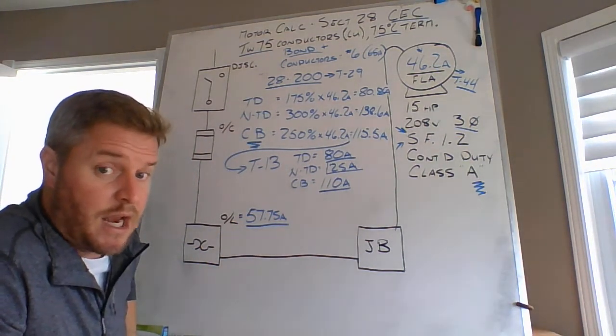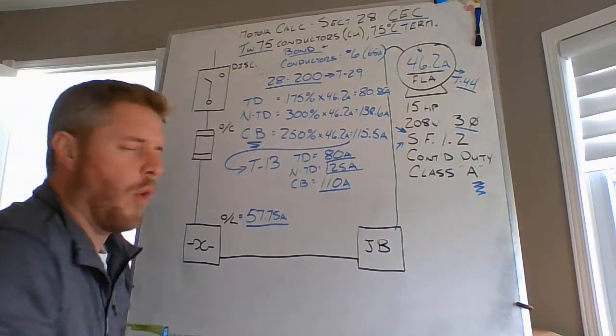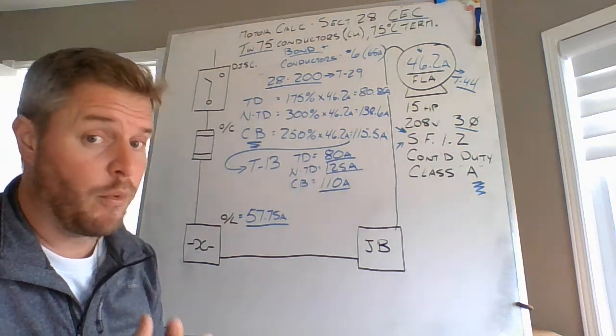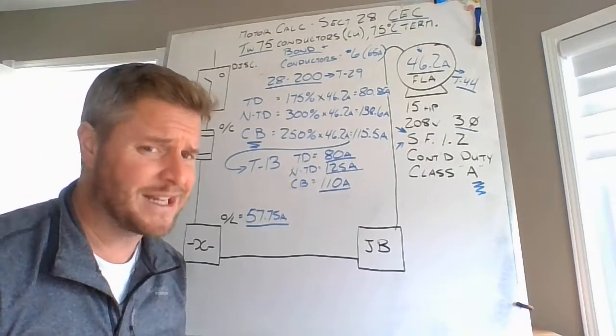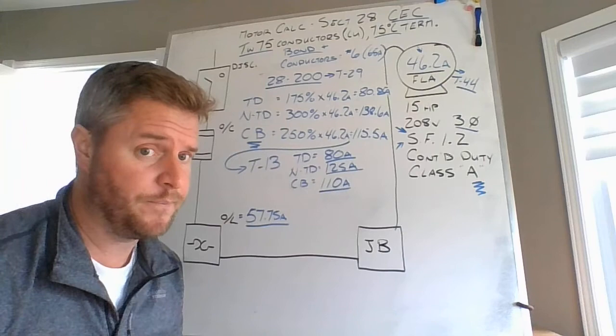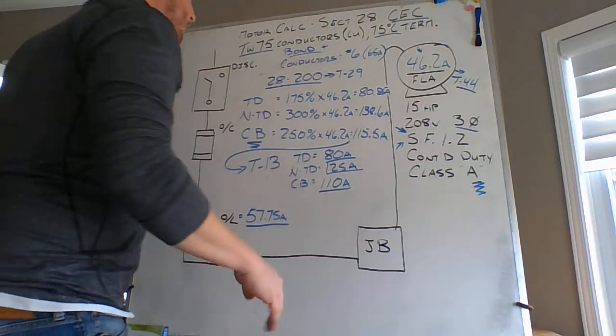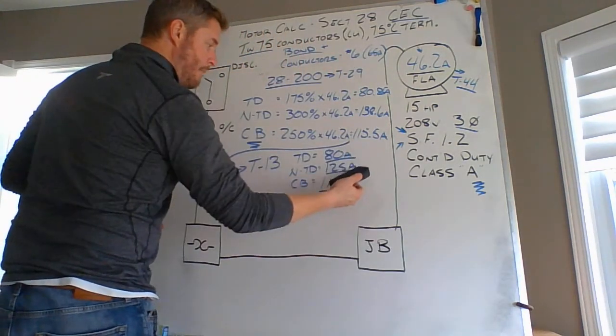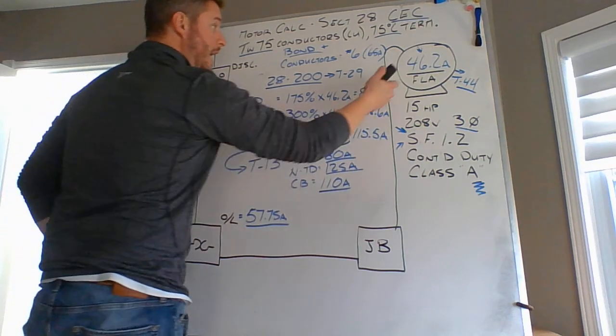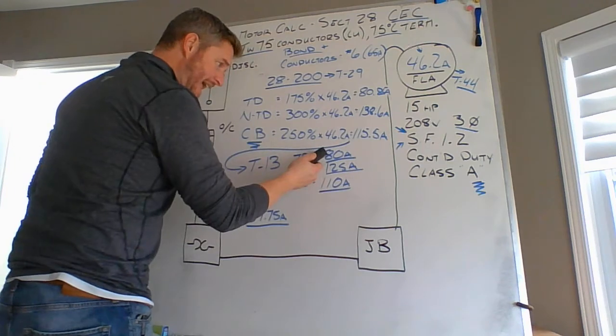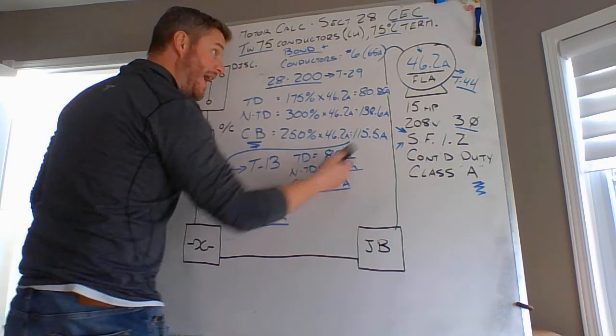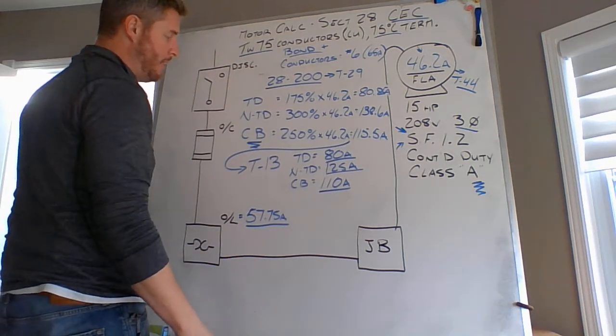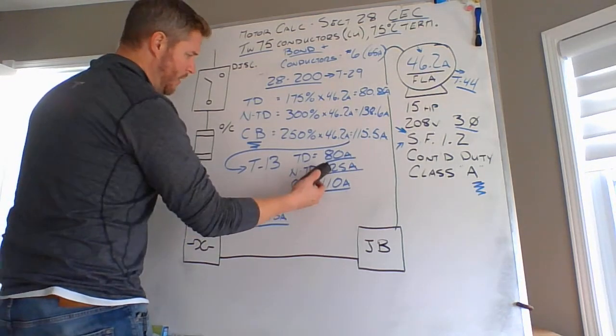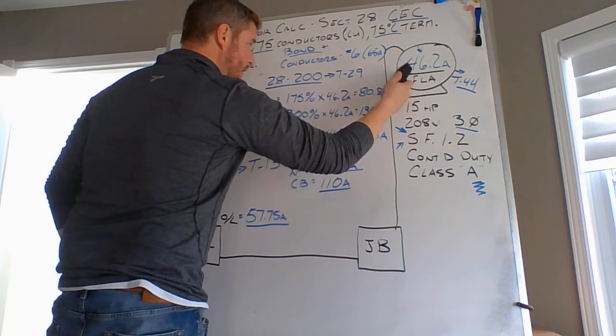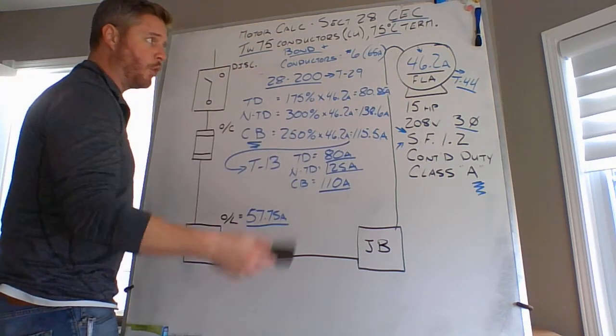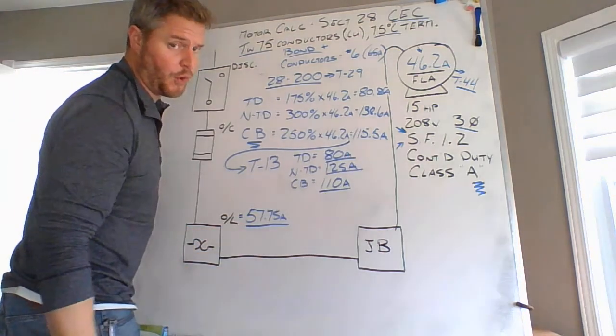Okay. Here's how you determine this in the field. All right. It depends upon which style of overcurrent device that you're going to install. And I want you to observe this just for a second because we're going to talk about real installations, real things that happen in real life. What ends up happening with your installed overcurrent devices being an 80 amp, a 125, or a 110 for a 46.2 amp motor. 80 amps for a 46.2 amp motor, 125 for a 46.2 amp motor. Come on, man, give me a break. Really? That's 300% the full load current rating of that motor. You have to understand that motor should never ever draw more than 46.2 amps.